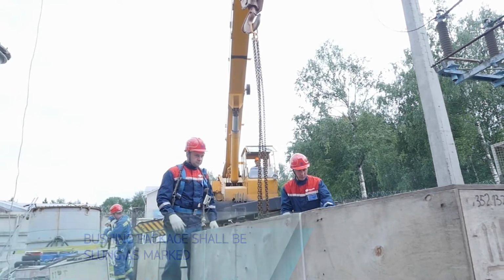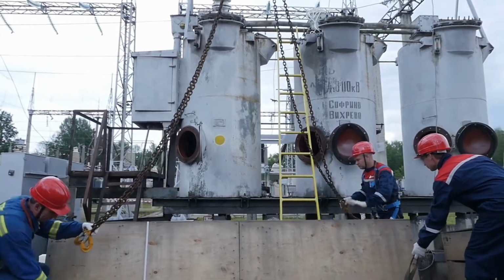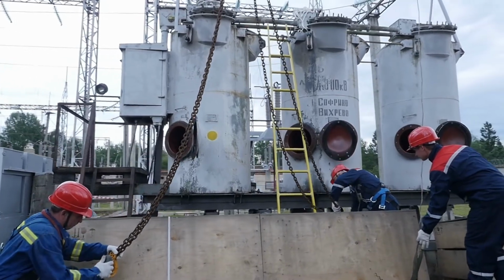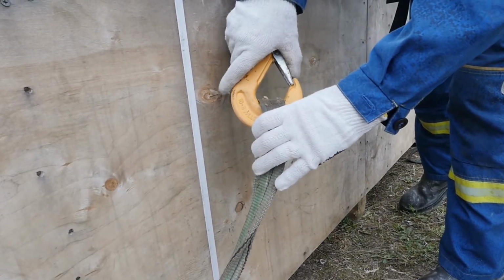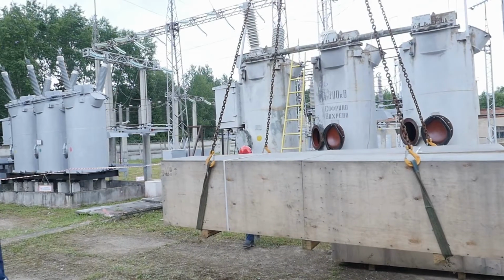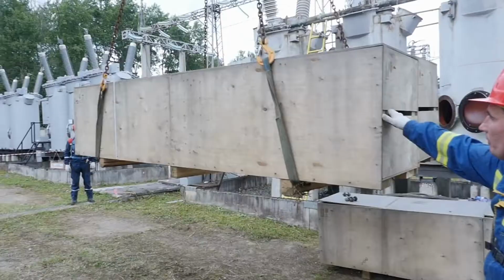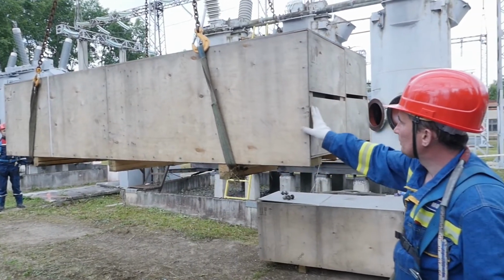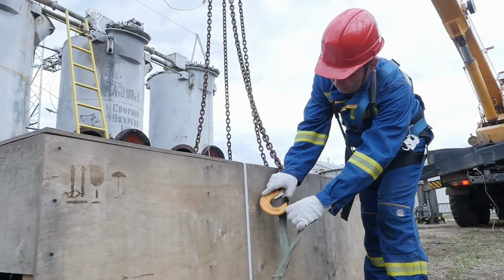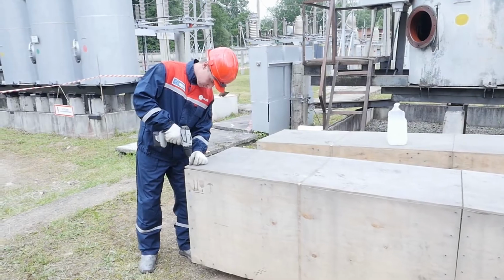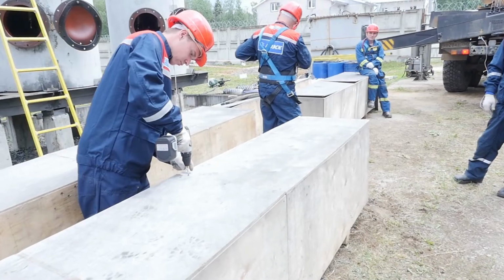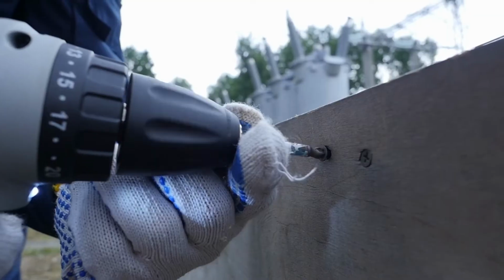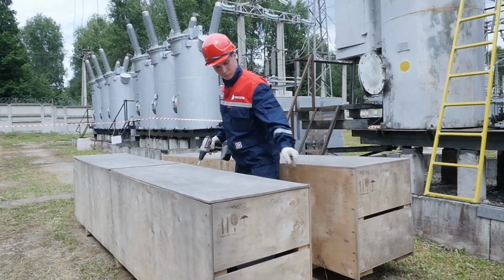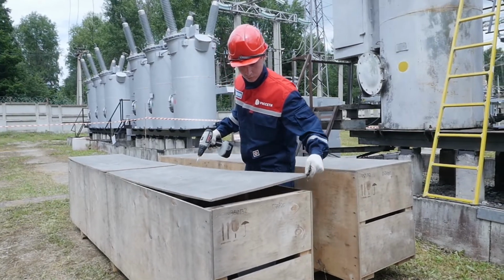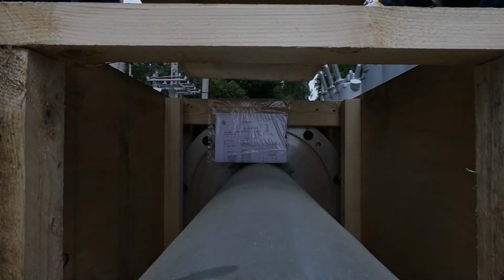To tie up the bushing package correctly, lead a sling under the box bottom and secure it to a crane hook on one side first and then on another. Slightly hoist the box over the floor and make sure it is balanced. Only then the package can be moved to a necessary place. Remove sealing tapes and a box cover by loosening the self-tapping screws securing the cover to the sideboards. Based on bushing dimensions, the cover can be made of one or more plywood sheets and, if necessary, it can be used for packing a bushing later again. For that purpose, we recommend keeping the cover screws in an intended place.